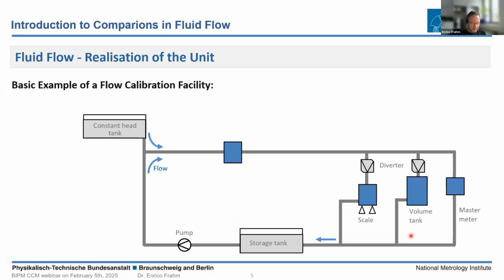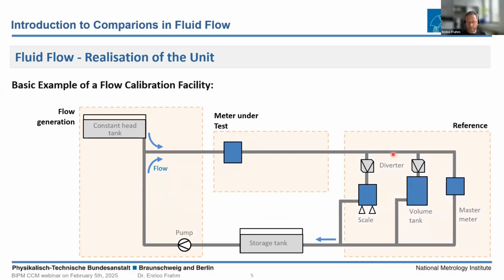So this basic principle applies to a flow calibration facility. There's a flow generation section required, like a pump or constant head tank. The fluid passes through the meter under test and the reference. These are some examples of typical references used in a fluid facility: it could be a scale, a volume tank, or a master meter. And finally, the water flows back in the circle into the pump via a storage tank.